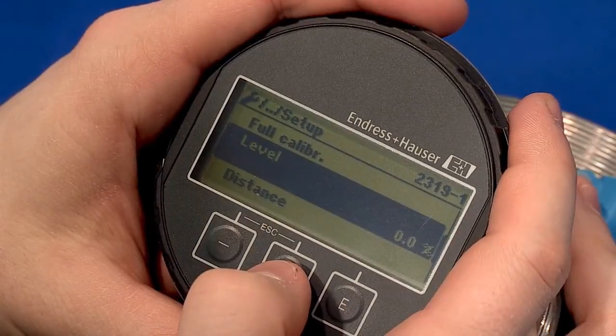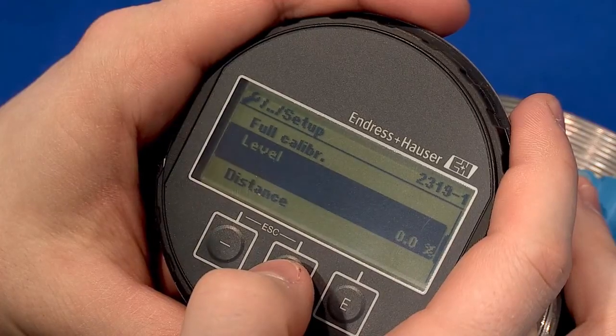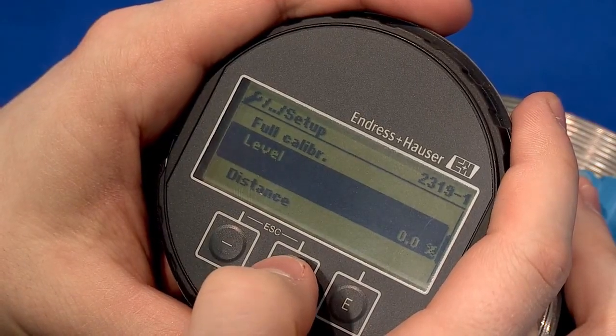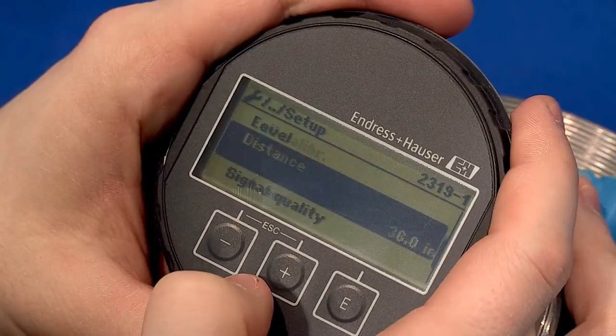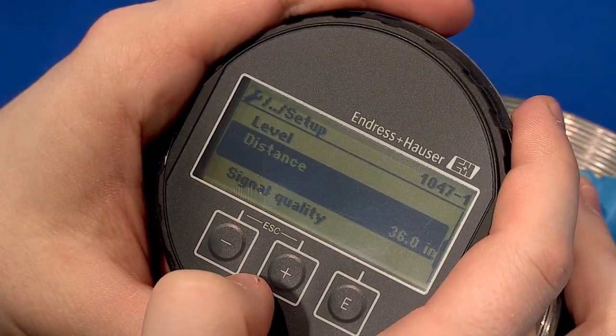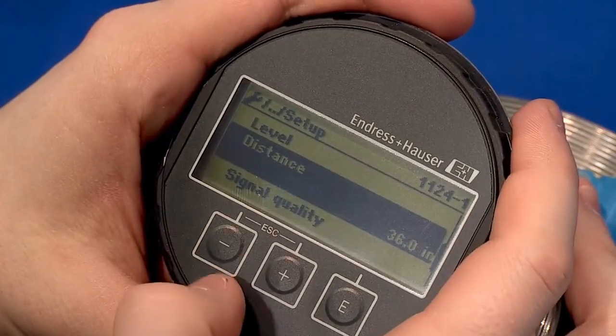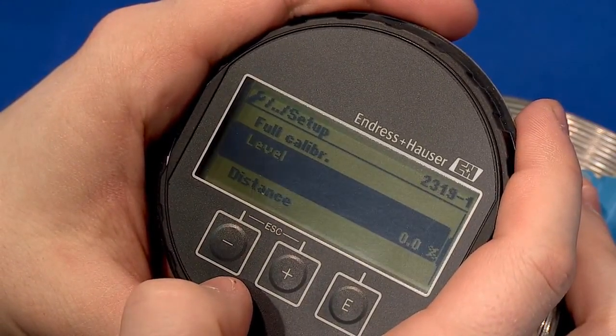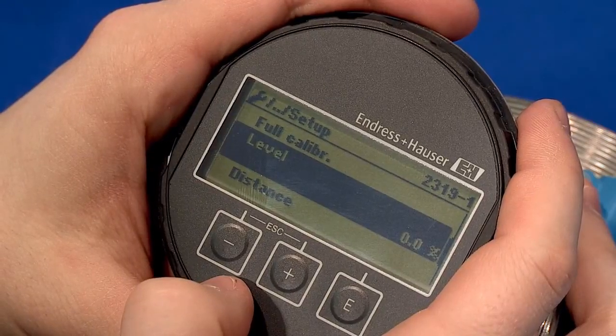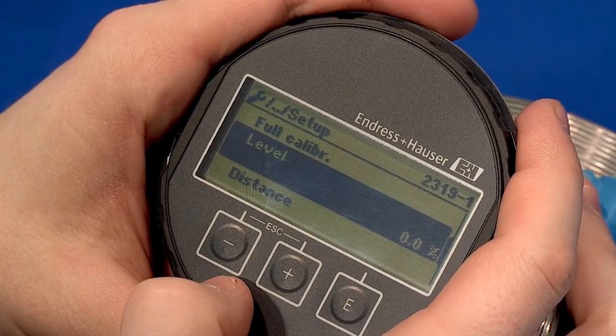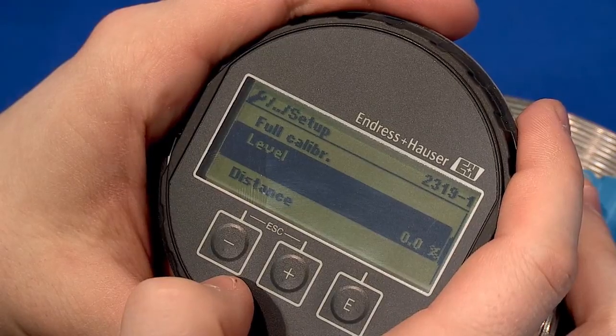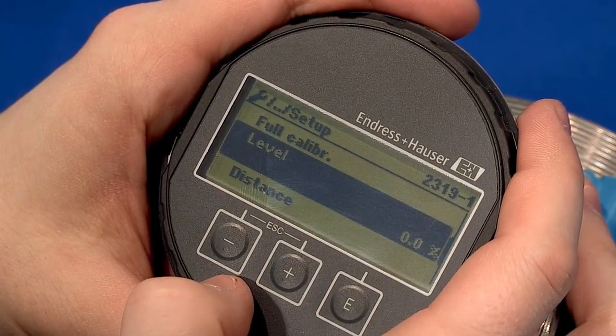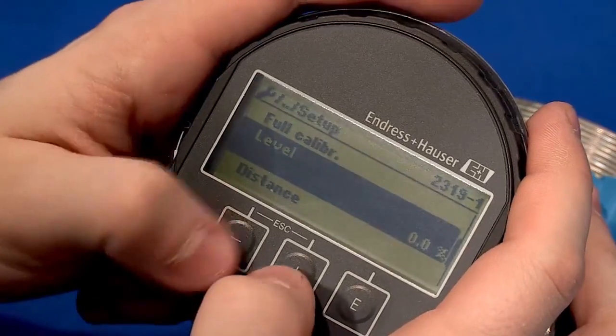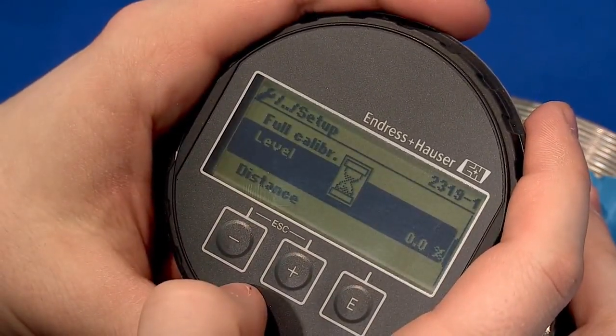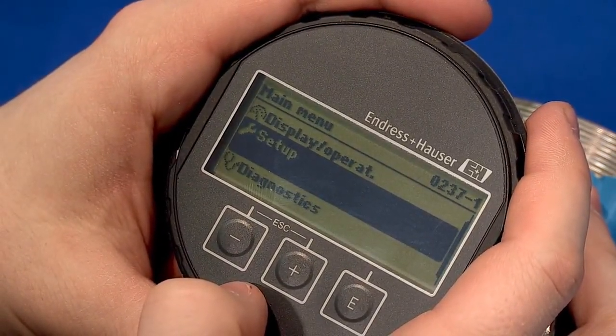The next two parameters, level and distance, are read-only values. The distance value is the distance that the unit actually sees from the process connection to the top of the product, or the empty space in the tank. The level is a calculated value found by subtracting the distance from the empty calibration. If your distance and level values are reading correctly, you have successfully set up your instrument. You may now press the plus and minus keys together at the same time to return to the main menu. If your instrument is not reading correctly, you may need to do mapping.